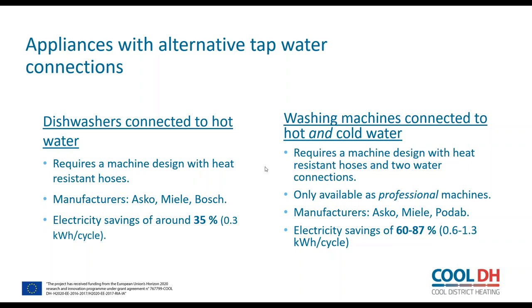If we start with dishwashers, the use is limited by how heat resistant the hoses are. And we found three manufacturers that claim that their dishwashers are heat resistant. And these are Asko, Miele, and Bosch. And they can withstand temperatures of 70, 60, and 60 degrees Celsius, respectively. Installing one of these machines would give an average electricity reduction of 35% or 0.3 kilowatt hours per cycle.